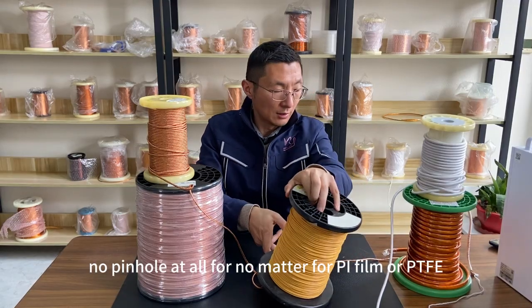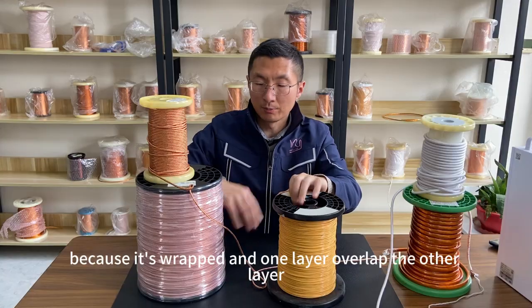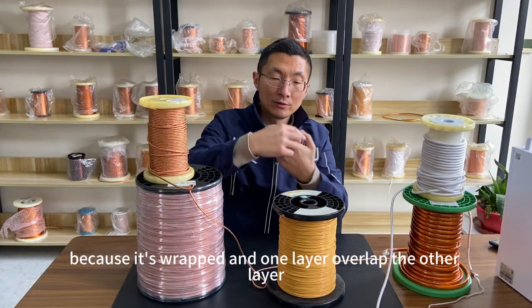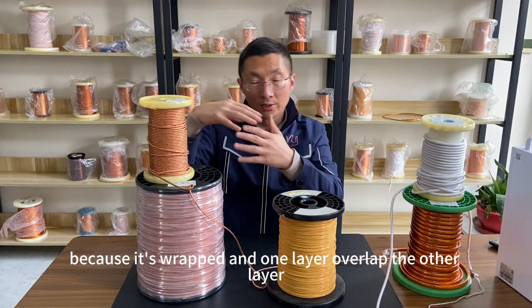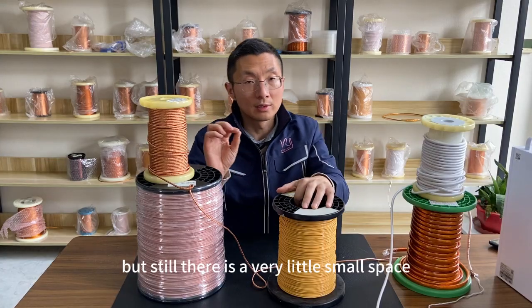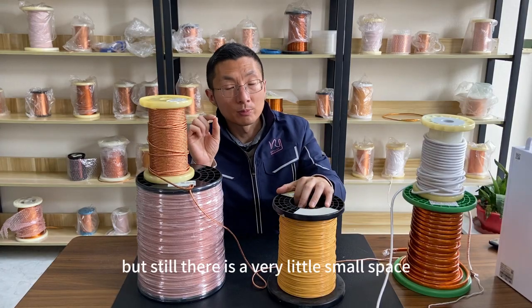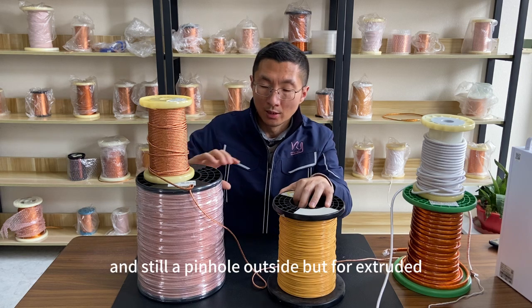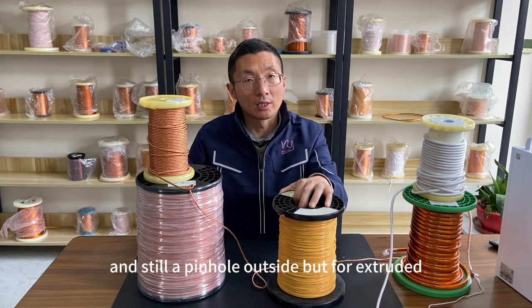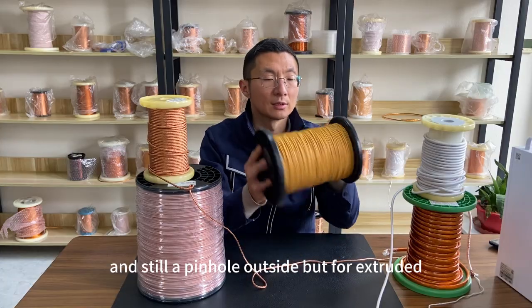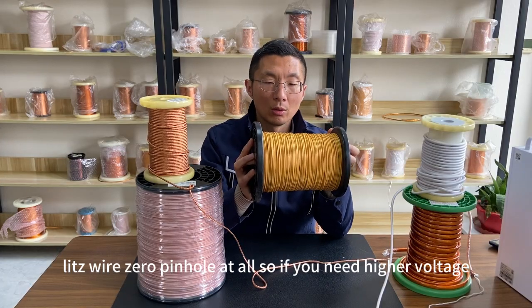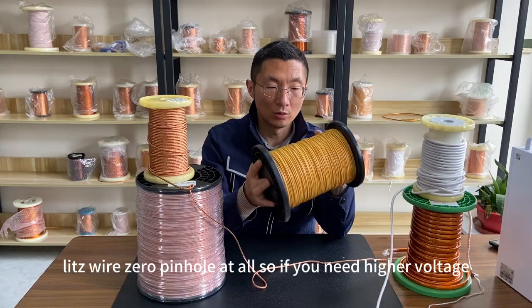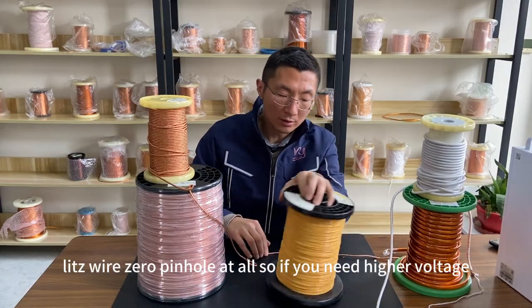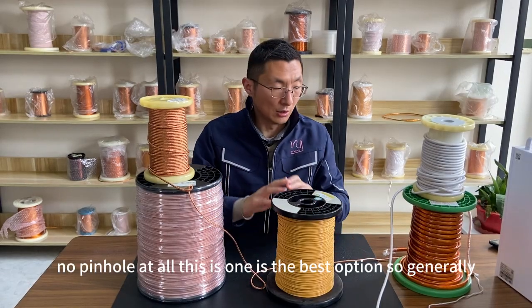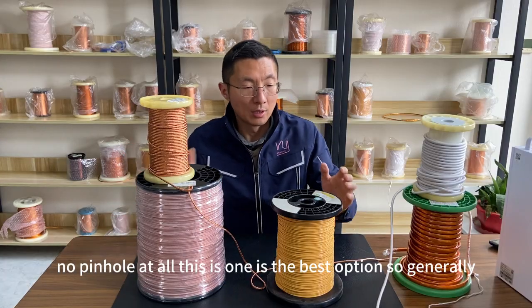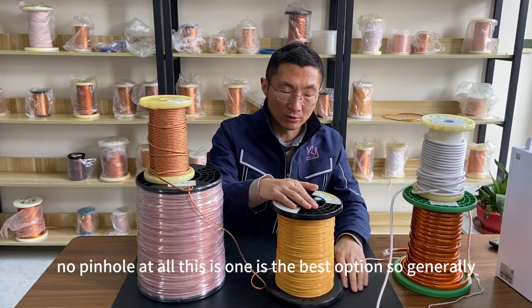For PI film or PTFE, because it's wrapped and one layer overlaps the other layer, there is still a very small space and still a pinhole outside. But for extruded litz wire, there is zero pinhole at all. So if you need higher voltage and no pinhole at all, this is the best option.